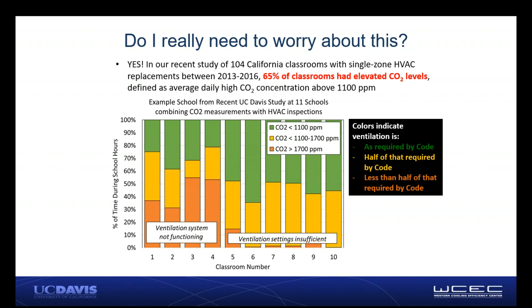So where does it go wrong? We spent a lot of time looking at why 65% of those classrooms didn't have adequate ventilation, and there's a whole host of reasons. I want to go through all of those so that when you're considering HVAC replacements as part of your zero net energy plans, you can think about how not to make these mistakes in installing your systems. There are basically four things that have to go right. One, you have to select equipment that is capable of providing ventilation rates for high occupant density classrooms. Classrooms have a lot of people packed in there, so you have to make sure equipment is capable of providing enough ventilation. That's step one.